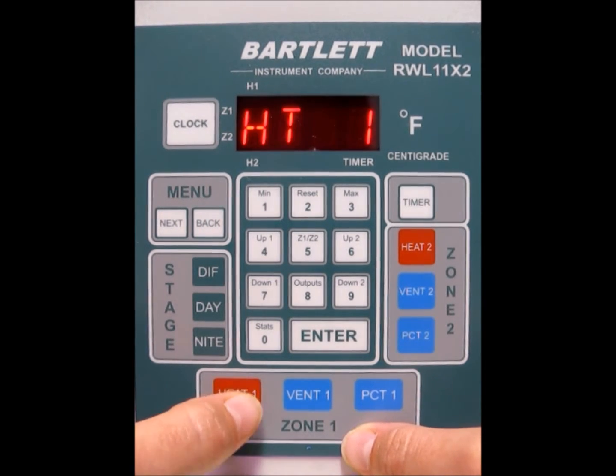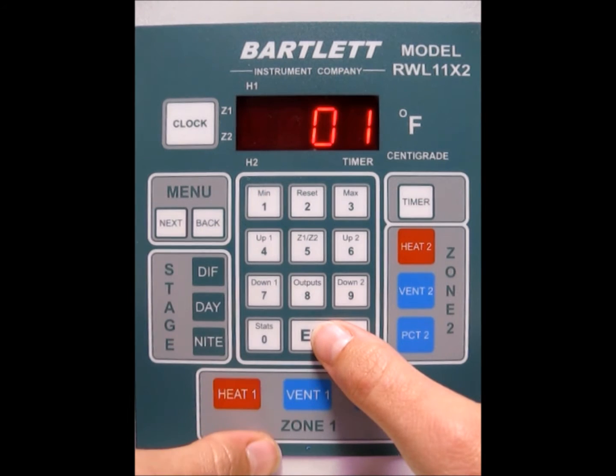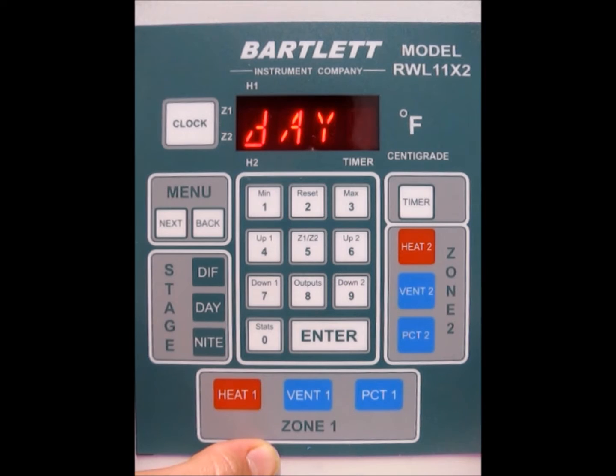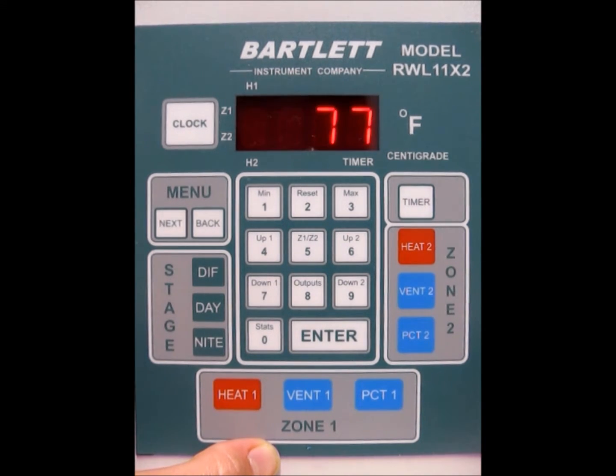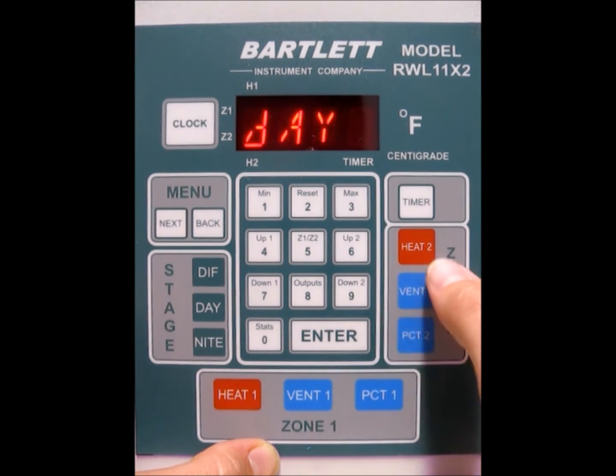Press heat 1 — it's set to auto, which is what we want. Press the enter button. Now it's asking for your step size for heat 1, so we're going to do a step size of 1. Press enter and we're back at the idle screen. For heat 1, it should come on at 76 degrees and turn off at 78, because our output temperature is now 77 and our hysteresis is 1 — it will do a degree above and below the output temperature when turning on and off.